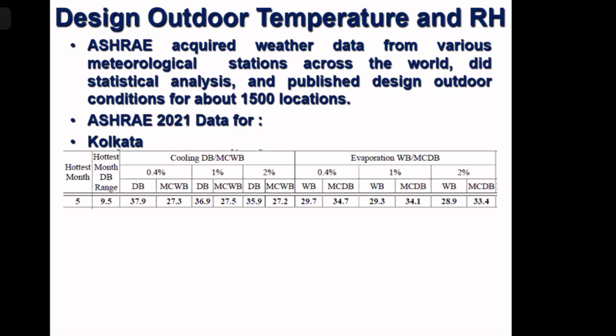For the cooling requirement, which will basically be used for air conditioning, we have 0.4%, 1%, 2%. These are occurrence levels. For 0.4%, we have dry bulb temperature and mean coincident wet bulb temperature. If we select 0.4% dry bulb temperature for Kolkata, it is 37.9. So if we consider the design outdoor dry bulb temperature for Kolkata as 37.9 degrees centigrade, then over the reasonable life cycle of the AC plant, only 0.4% of the time will the outdoor dry bulb temperature exceed 37.9. So we call it 0.4% occurrence level.